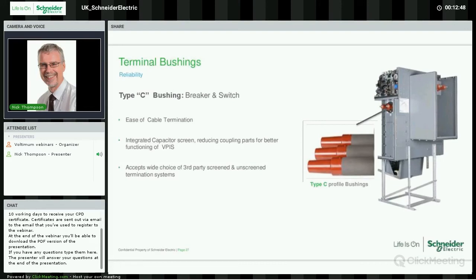Inside that bushing, on each of the three bushings, there is a screen embedded, or cast into the pole, and it's then connected to a cable which is then going to be used for the VPIS, which is the Voltage Presence Indication System. It's only a simple device which allows you a visible indication of a potentially live circuit.